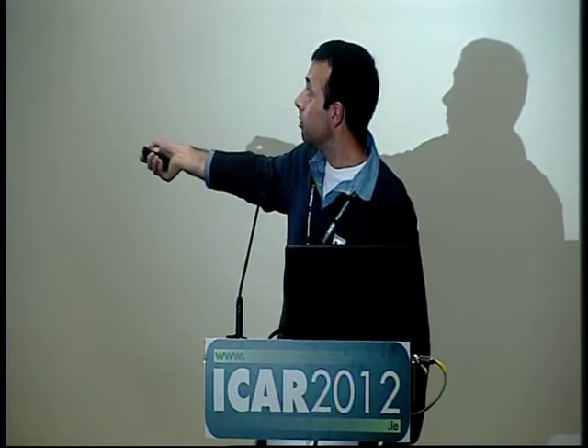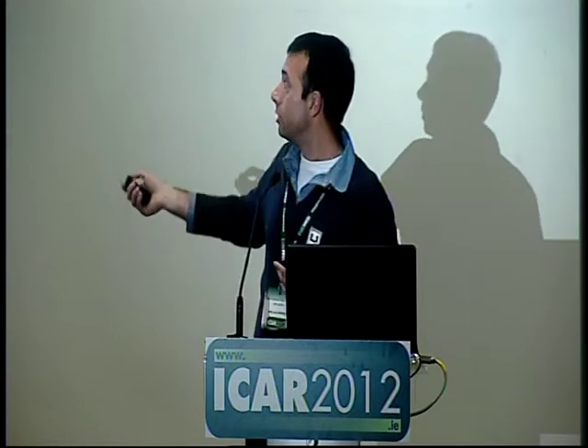And then people also received a sucrose sample and a standard sample that is a kind of detergent or something like that. This is just to be sure that the slave instrument is stable over time. Because, for instance, sucrose is something where the peaks appear always in the same place. So people have to be sure that they always have the same peak. In that case, we are sure that the instrument is not moving.